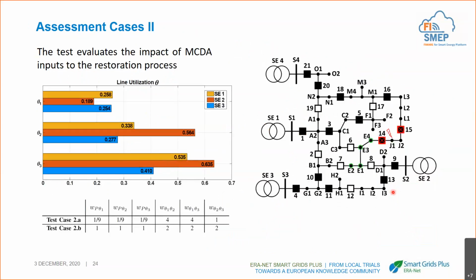In the second test case, we didn't consider only the power losses, but also the utilization of the electrical lines with the parameter theta that I explained before. And in case we have a fault here and these de-energized loads, we can reconnect them by closing the switch 6, 7, or 8. If we give much more importance to the utilization of the electrical lines, and we don't give importance to the power losses, the best solution is via this switch. In case we also consider the power losses, so in the case 2B, for the final solution, we close the switch 8, as we see here.